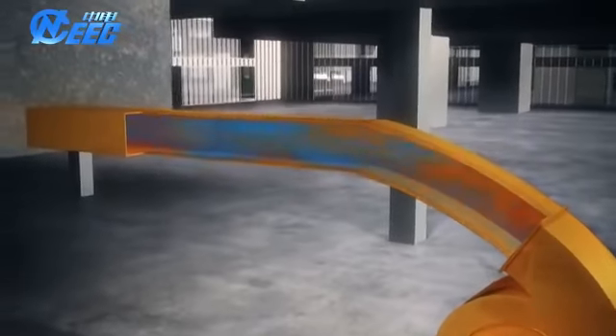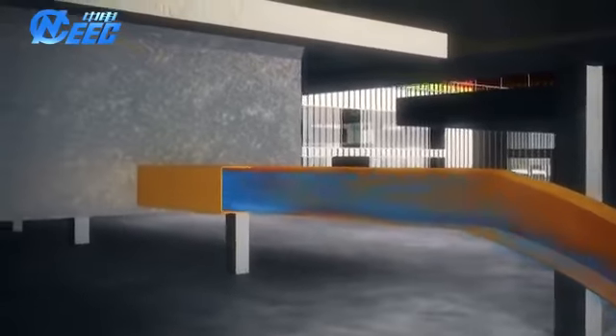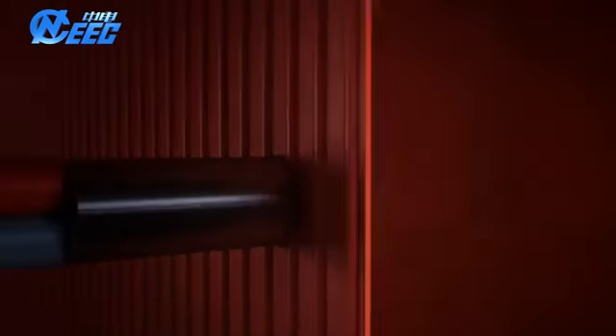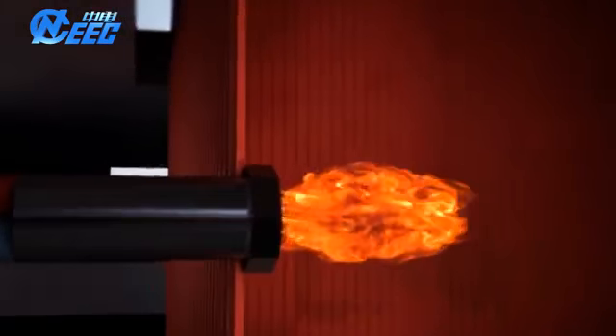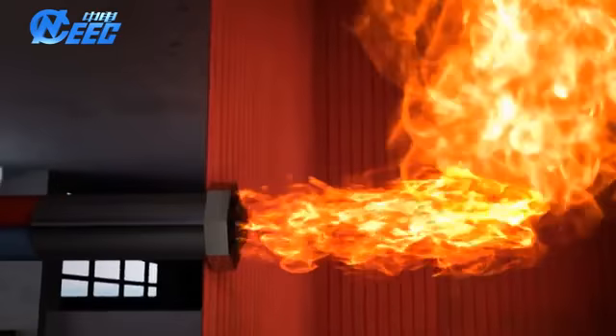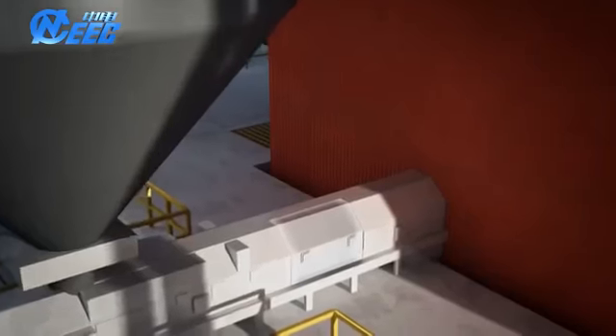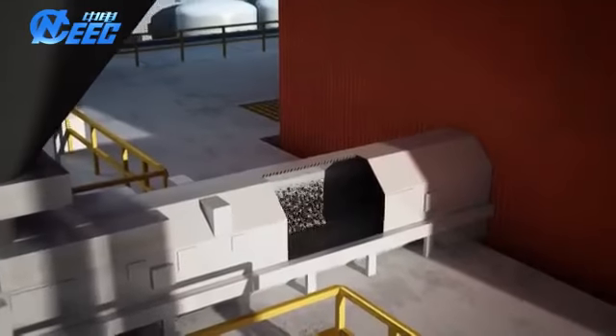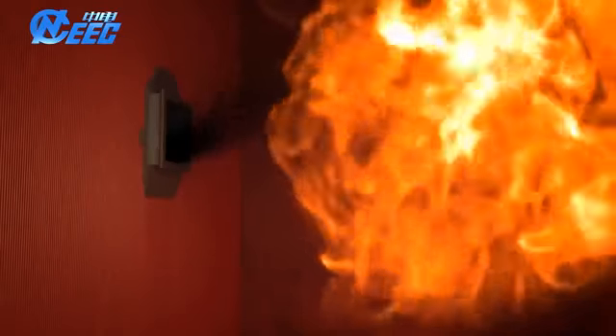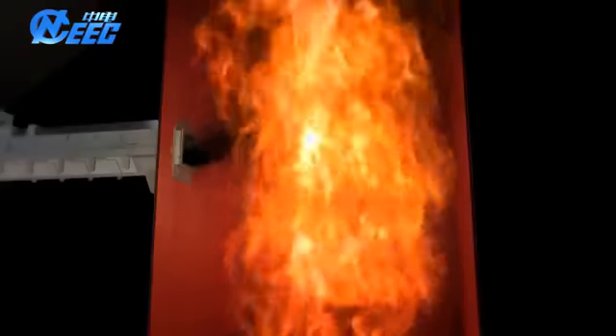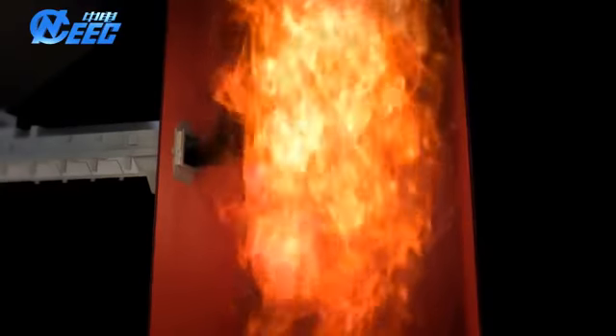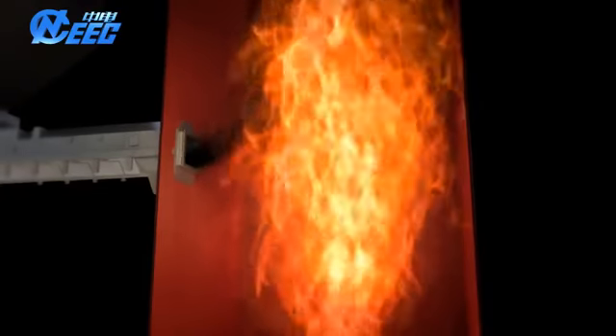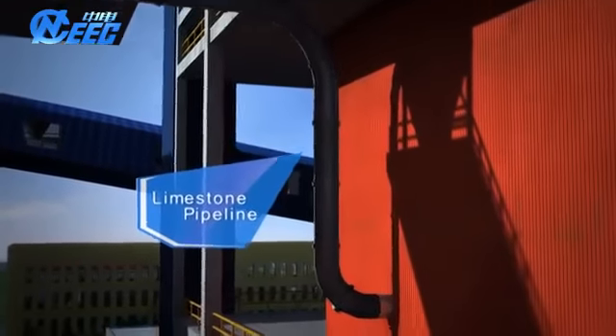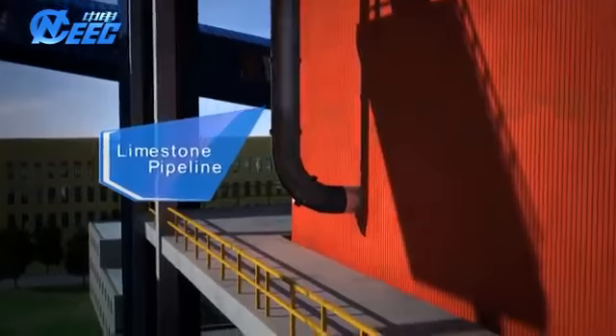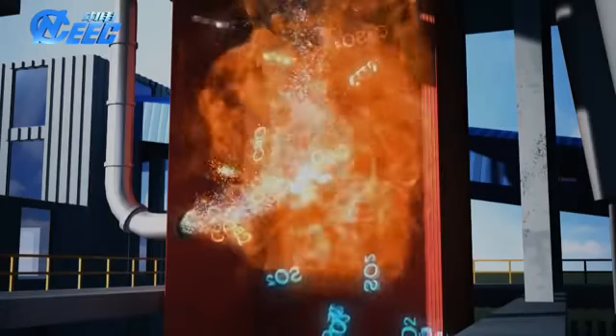Startup induced draft fan, forced draft fan, and primary air fan. Air is forced into the combustion chamber. Diesel oil is ignited by high-energy ignition gun and burning in combustion chamber. Coal feeder transport coal powder into coal pipe, and coal powder is forced into combustion chamber by primary air. Powder coal is ignited by oil torch. With limestone powder feeders running, limestone powder is fed and blown into combustion chamber by compressed air.